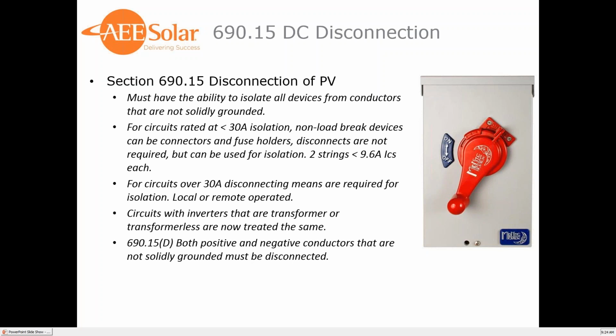So if you have 2 strings that you're combining, are you required to have a disconnect? For circuits over 30 amps, disconnecting means are required for isolation. What that sounds like is if you're doing any type of combining, you need to have a disconnecting combiner, essentially. It could be local or remote operated. So if you're combining, depending on how the interpretation is, 2 or 3 or more strings and coming down to the inverter, it would be required to be a disconnecting combiner. And still only fusing is required on one side, either the positive or the negative, but both conductors must be disconnected.